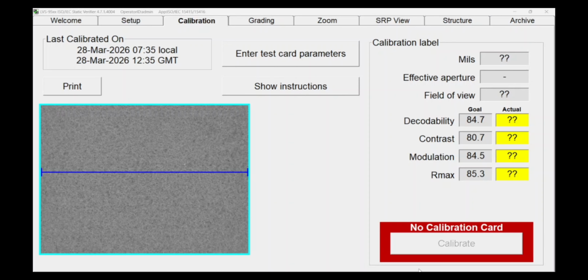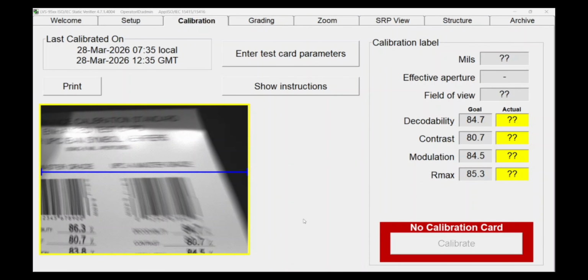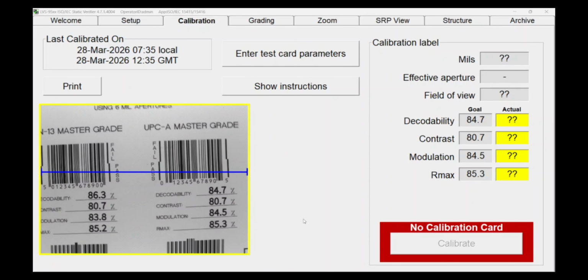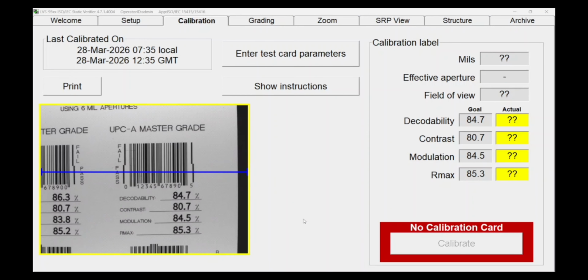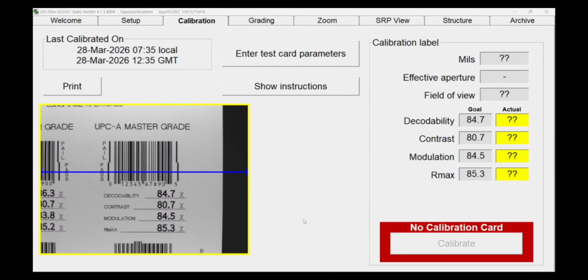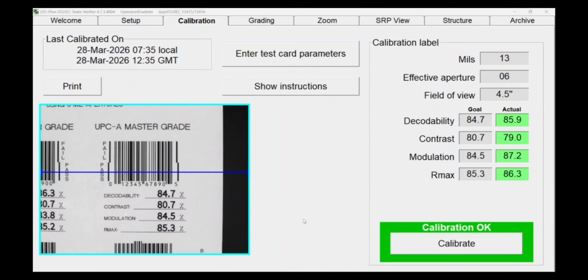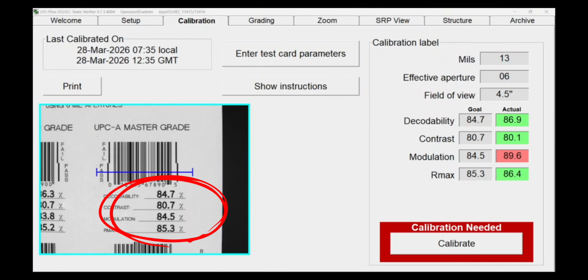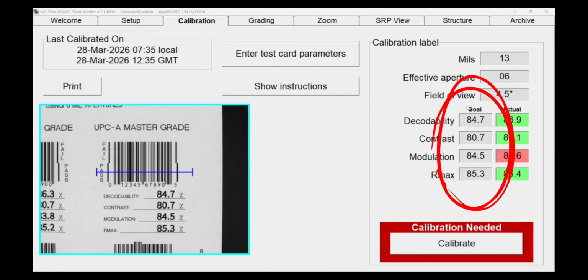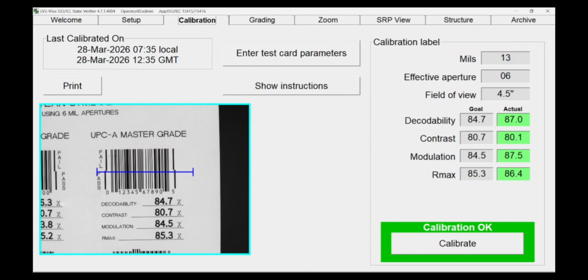Make sure your glass is clean of dust or smudges, and then place the conformance card on top of the window. You want to line up the horizontal blue bar to be under the pass portion of the code. Ensure the values on your conformance card match the values under the goal column. So the values on this card here should match exactly what's shown here. If they do not, you can click on Enter Test Card Parameters to make those adjustments.